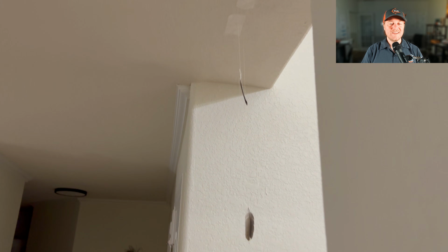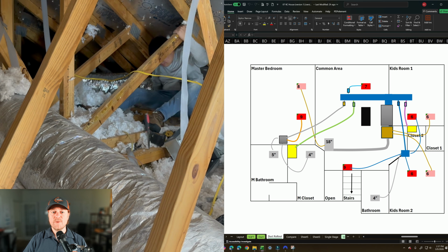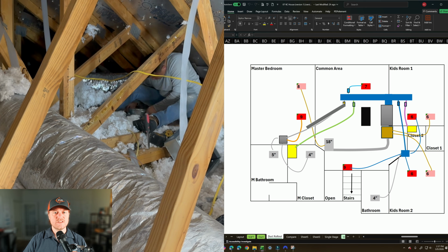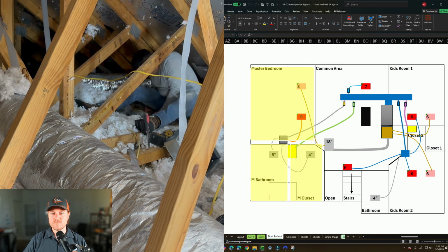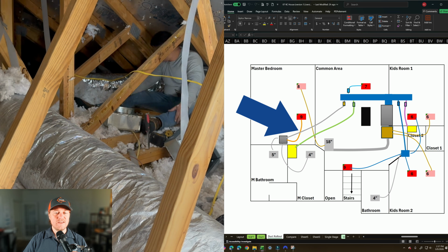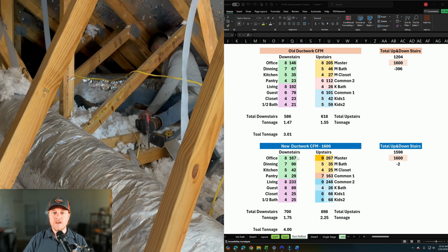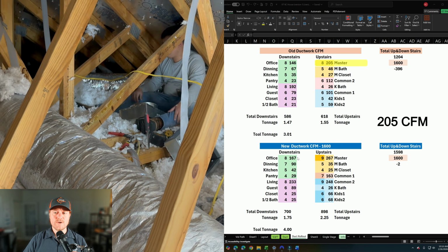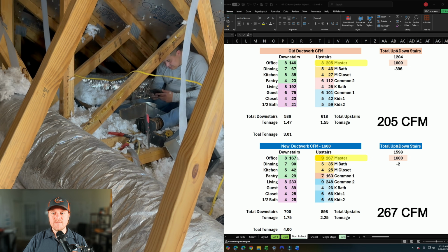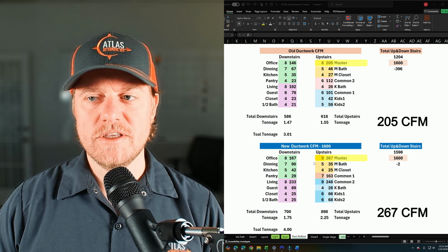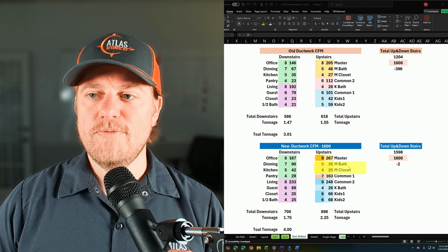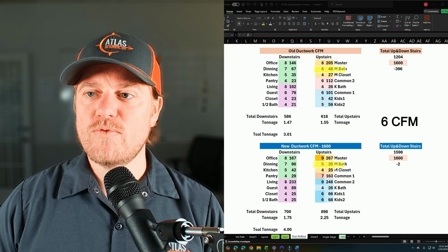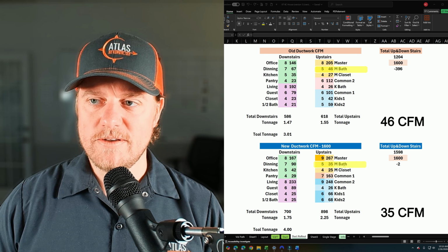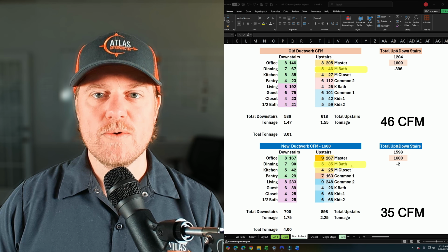Now let's take a look at the upstairs master bedrooms. In both of these scenarios, we have a 10-inch duct supplying a distribution box, which is breaking out, feeding these 3 rooms. And we replaced the 8-inch duct in the master bedroom with the 9-inch duct, and we can see that the CFM went from 205 to 267, which is an additional 62 CFM. Now the problem that I'm seeing here are these 2 rooms here. If you notice, the master bathroom went from 46 CFM to 35 CFM. So there's actually less airflow in both of these rooms.